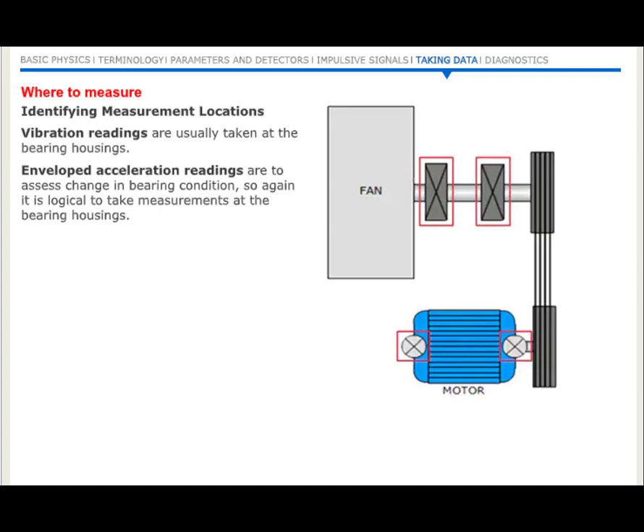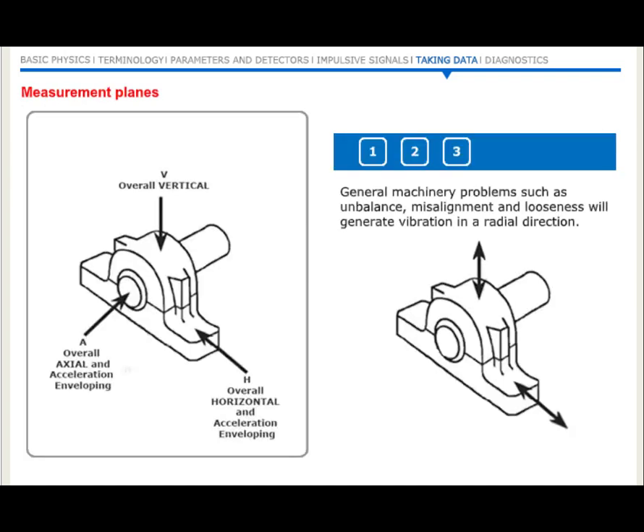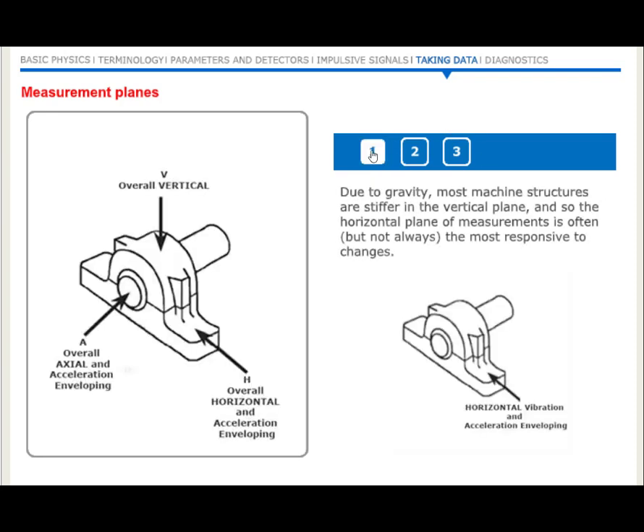Enveloped acceleration readings are to assess change in bearing condition, so again it is logical to take measurements at the bearing housings. Where machines include a gearbox, then enveloped acceleration signals generated by gear meshing will also be detectable at the housings of the supporting shaft bearings. General machinery problems such as unbalance, misalignment and looseness will generate vibration in a radial direction. Due to gravity, most machine structures are stiffer in the vertical plane, and so the horizontal plane of measurements is often, but not always, the most responsive to changes.